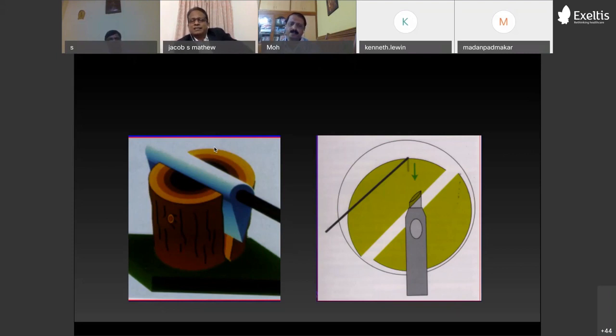Initially, select a cataract that is about grade 2 or 3. It should be hard enough. It should not be very soft, because you will sort of cut through. So, initially choose grade 2 or 3 hardness, not a very hard cataract. And then you are able to go towards the equator of the nucleus, which may not be right up to the extent of the capsule equator. So it's safe that way, and go right to the equator, and then bring the tip of the chopper towards the phaco tip as you're holding the nucleus at that part of the center of the nucleus.